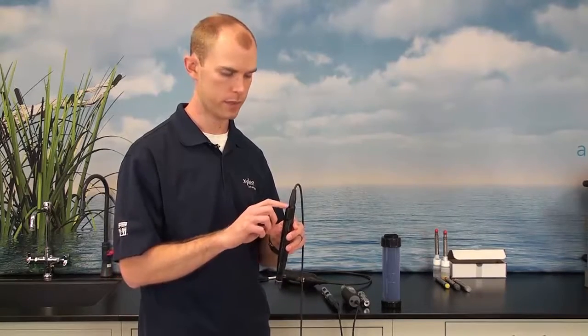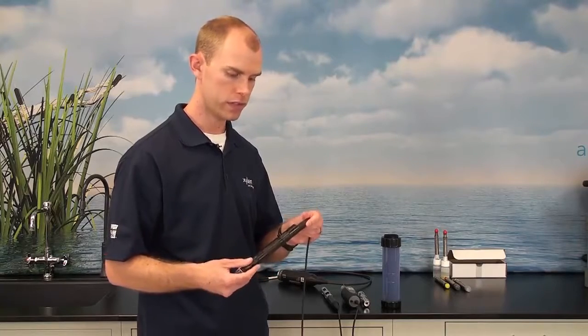It features a built-in conductivity cell at the top of the probe here, and an optical DO sensor at the bottom portion, right here. It also features a built-in thermistor for measuring temperature. This cable is available in up to 100-meter lengths, but there is no depth option with these cables.